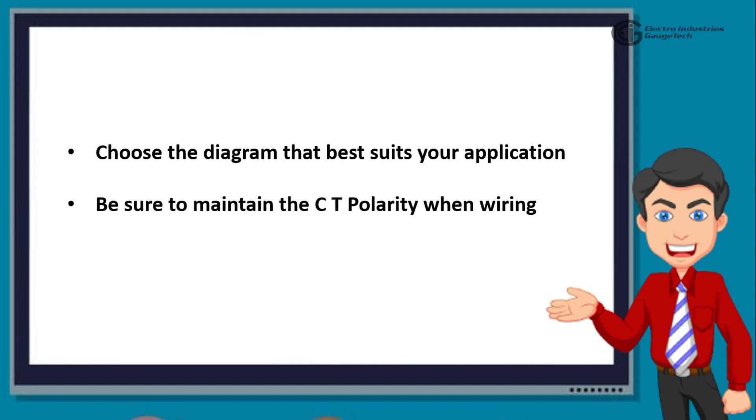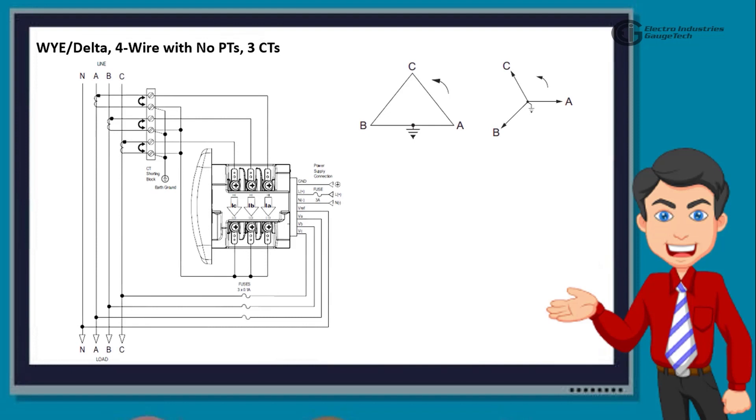The next section we'll cover is the electrical connection diagrams for Shark 250 meters. Choose the diagram that best suits your application. Be sure to maintain the CT polarity when wiring. The first one is Y-Delta, 4 wire with no PTs, 3 CTs. The diagram clearly shows the 3 phase, 4 wire system Y-Delta with direct voltage, and 3 element. When using this wiring, select 3 L Y, that is, 3 element Y from the Shark Meter's front panel display.